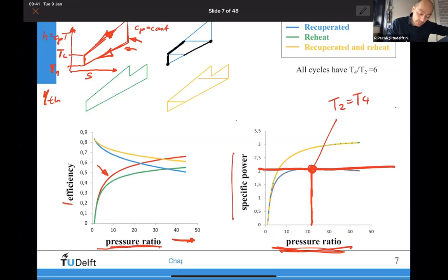So this exhaust heat of the turbine can be used either in a bottoming cycle, for example, in a combined cycle power plant where you have a gas turbine and a steam turbine, which means that this heat here goes to the steam turbine. But in this case, this heat from the turbine outlet temperature until you almost reach ambient temperature again is not going to the steam turbine, but goes to the recuperator, to the high pressure part.